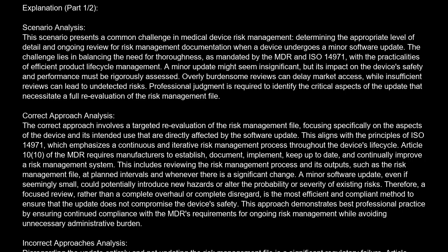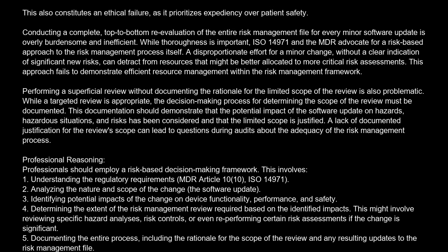A software update, by its nature, changes the device. Failing to assess the risk implications of this change means the risk management file no longer accurately reflects the device as placed on the market, violating the MDR's requirement for a continuously updated risk management system. This also constitutes an ethical failure, as it prioritizes expediency over patient safety.